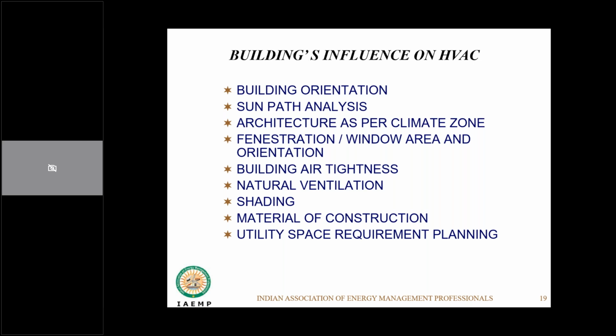And we need to understand the utility space and planning requirement. I think this is the least considered thing in building design, because HVAC is normally an afterthought after the space is done. Then we say, okay, isko air conditioning karna hai. Abhi kahan lagayenge? Where to put an air conditioner? Then you find a niche somewhere which has limited access and an unrealistic way of maintenance, and unfortunately this becomes our concern and basically a problem in long-term management of the HVAC system for that zone. So we should be very clear about what planning we need, how much space we need for HVAC, both for indoor and outdoor units, so that it can be done right.